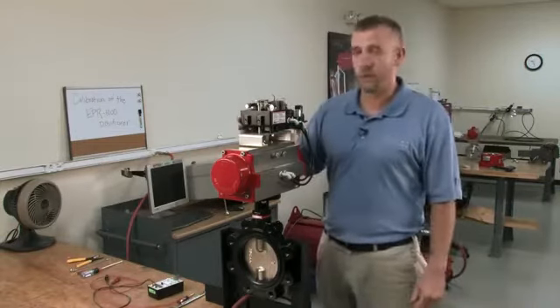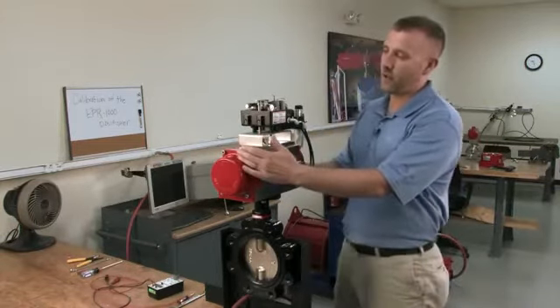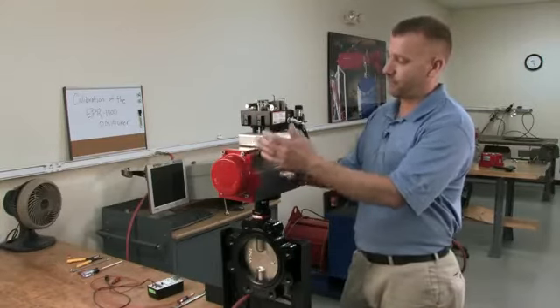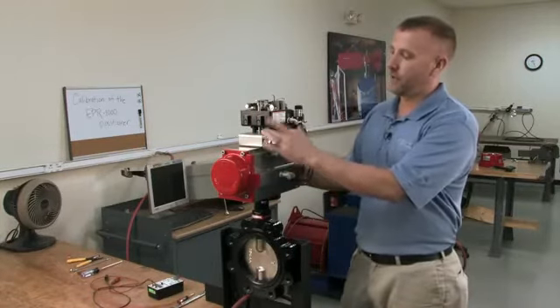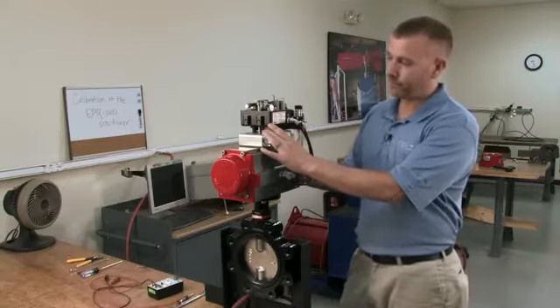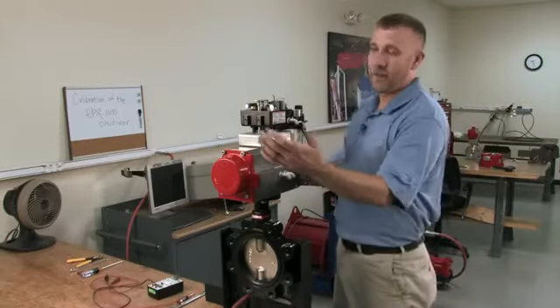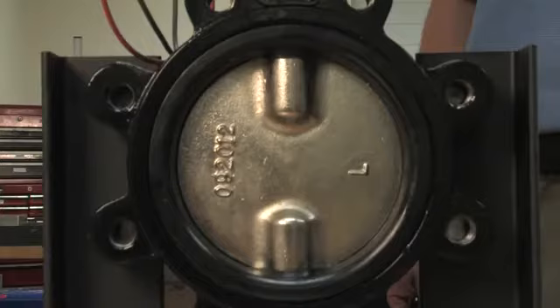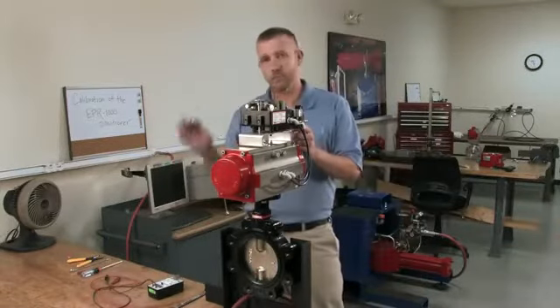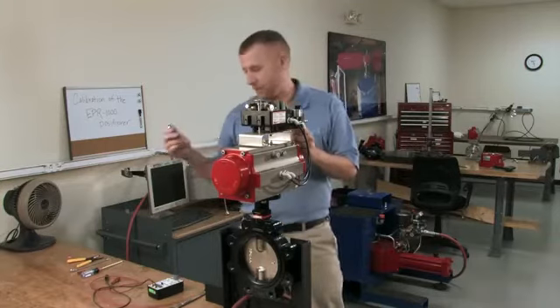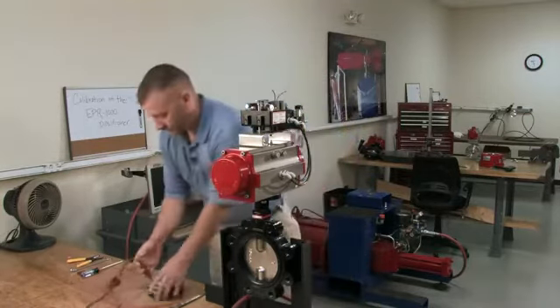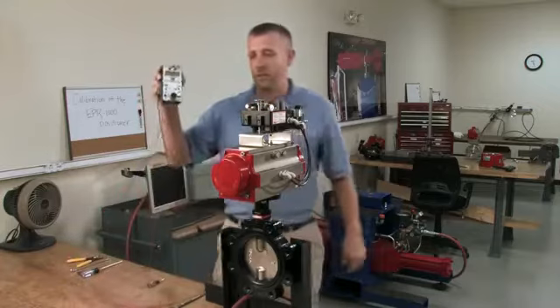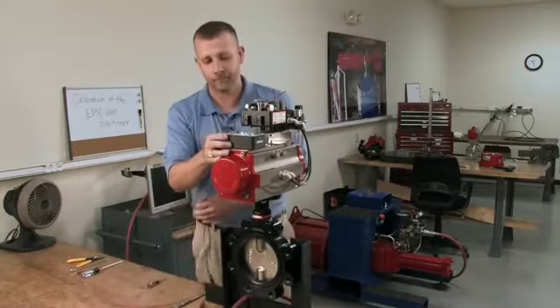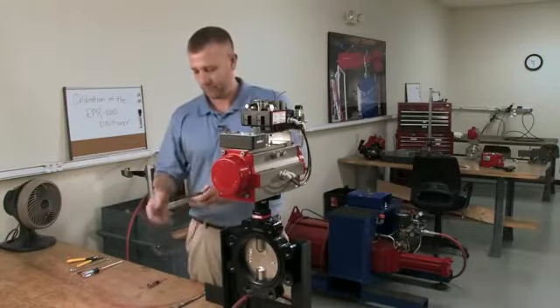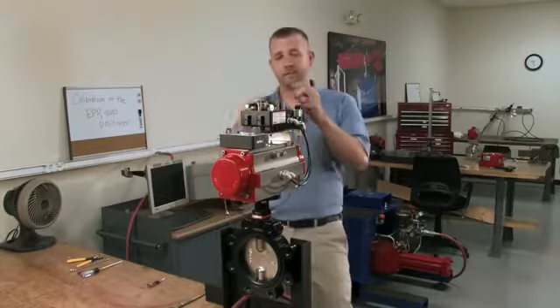This positioner is for our 2R300SR actuator, which is a rotary actuator. You can also get this for linear actuators. For this demonstration, obviously our 2R300SR and our 6-inch resilient seated butterfly valve. Okay, now I'm going to start hooking everything up just for a basic calibration. 4-20 milliamp handheld calibrator. Positive and negative.